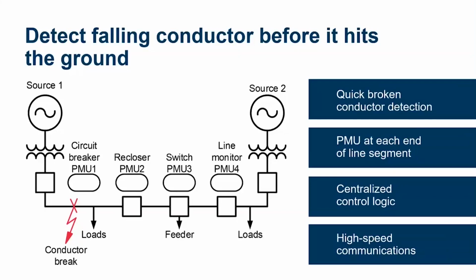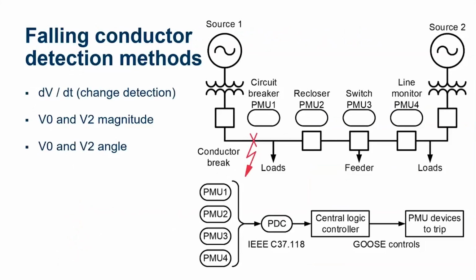Essentially, we compare the voltage between the two locations. We look for a sudden change of voltage between PMUs, so dV/dt is our primary detection method. We also have some backup methods looking at the negative and zero sequence voltage magnitudes and angles. All of this is sent to a centralized RTAC that's running this logic. It acts as a phasor data concentrator and then runs the centralized logic to detect a break.